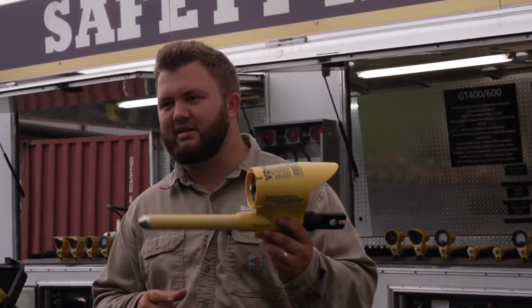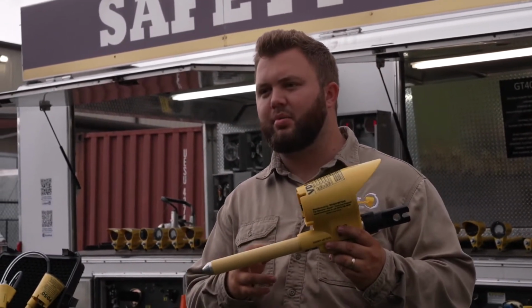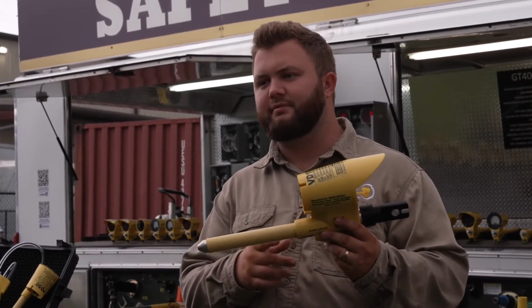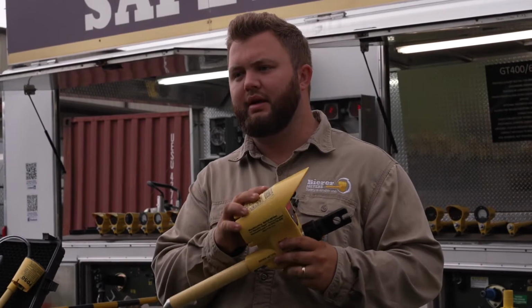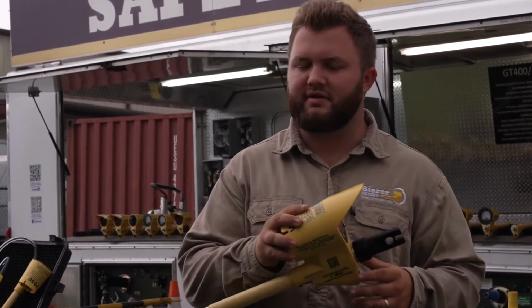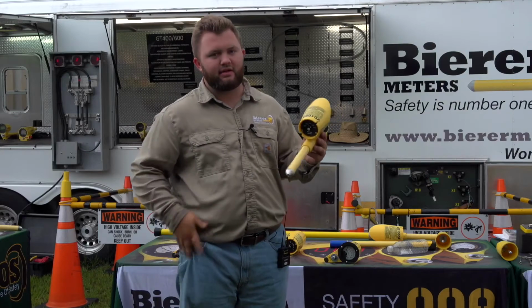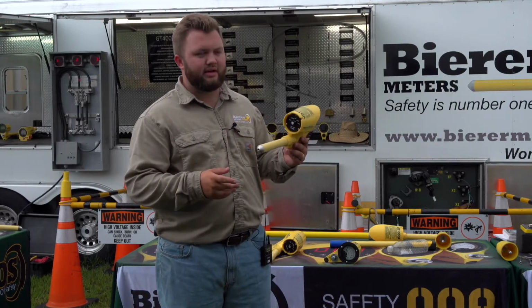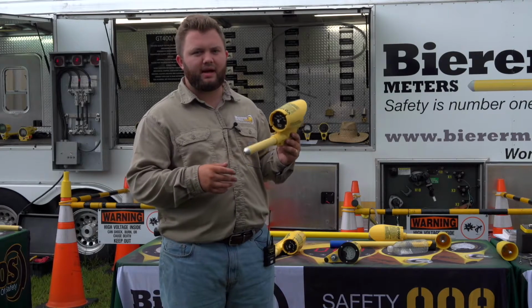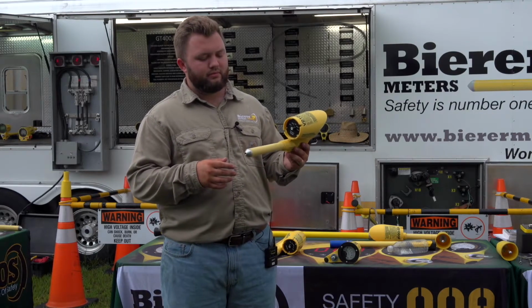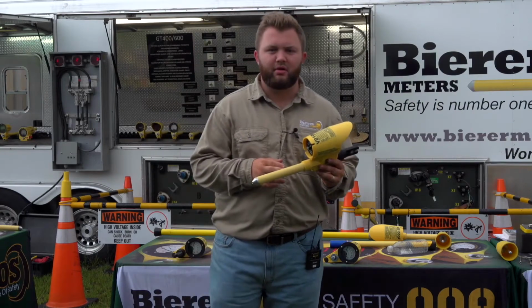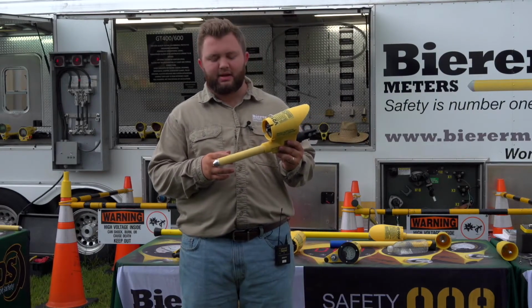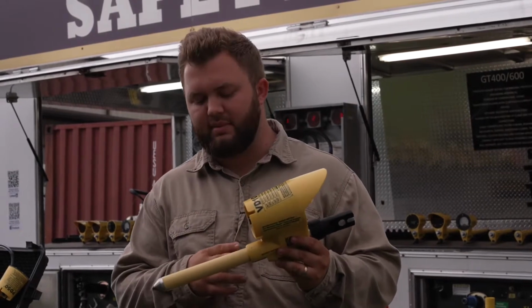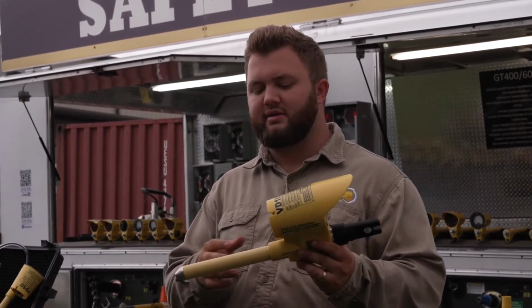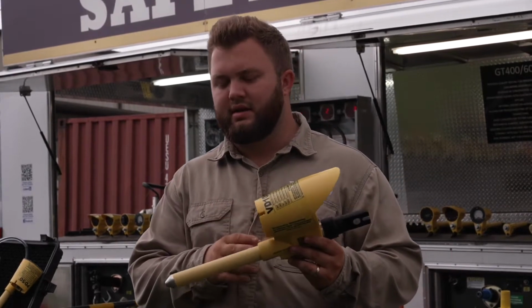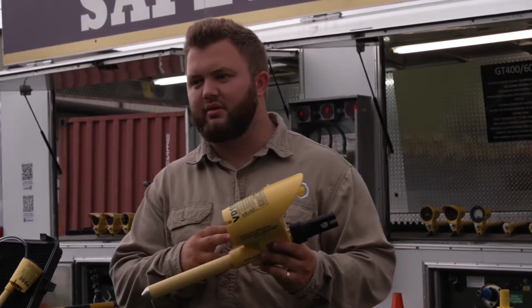What we do to make the tool safer, though, is we put resistors in the probe. Those resistors step down that current to make the tool a lot safer for you, and also safer as far as using the device in close proximity to grounds, hot conductors, whatever may be nearby the device. We also encapsulate those resistors in an epoxy. That epoxy is to keep out any dirt, grime, water that may get into the device, that would cause an internal track to those conductive components. So by doing that, we limit the potential of an internal track.